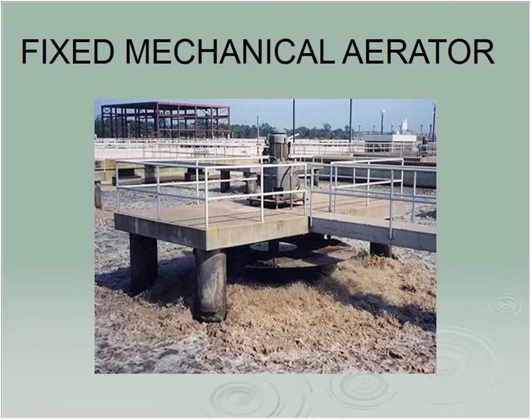This is increasingly disappearing from processes for a couple of reasons. For one thing, part of the process here, in addition to removing the BOD, is we need to remove those suspended solids, the colloidal stuff that's just hanging around. So the bugs will do that. They'll stick to that sugary substance on their bodies, and we want to form these nice, large floc particles that we see under the microscope. We'll see that later. Because the larger the floc particle, the more mass, the better it settles.